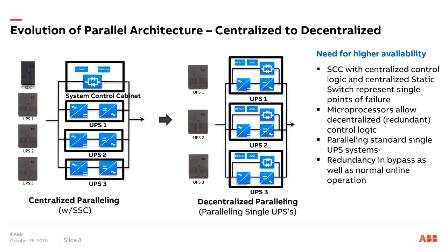So I say this because centralized paralleling came decades ago, and decentralized has easily been 2 or 3 decades back since it was first developed. And I believe there's actually still one manufacturer out there offering centralized paralleling. This was a backbone in large data centers in the US for at least a couple of decades. And some customers are very comfortable with having a big static switch that is rated for the full load. Typically, that would be 4 750 kVAs in parallel, and the static switch would be rated at 3000 amps.